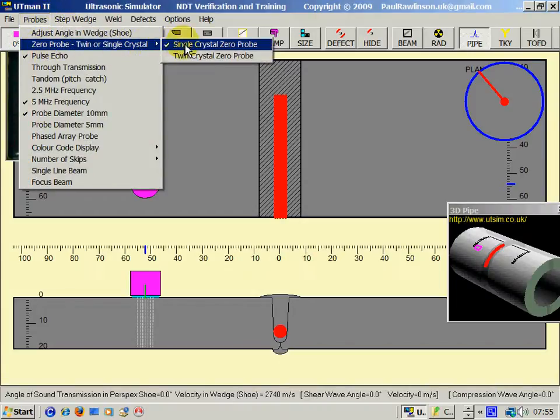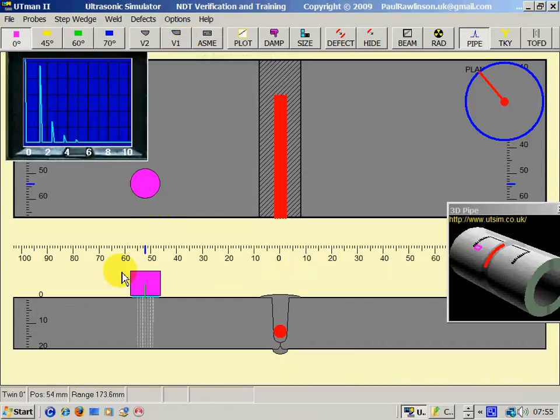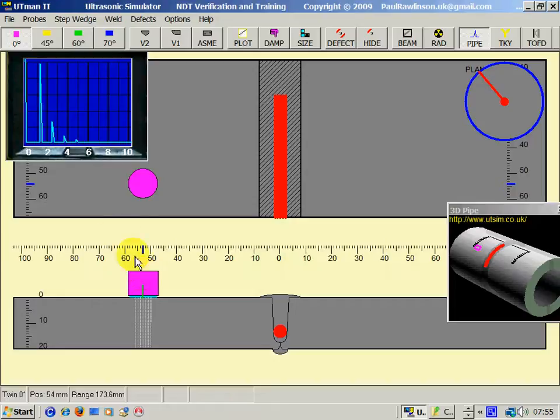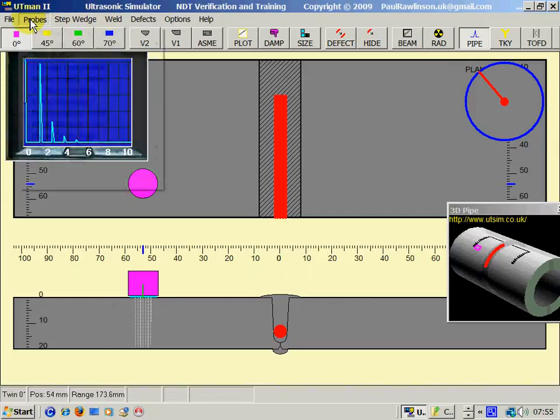Zero, which is a single crystal, and a twin crystal. The main difference is, with the twin crystal, we lose a lot of our initial pulse so we can read more of the screen.